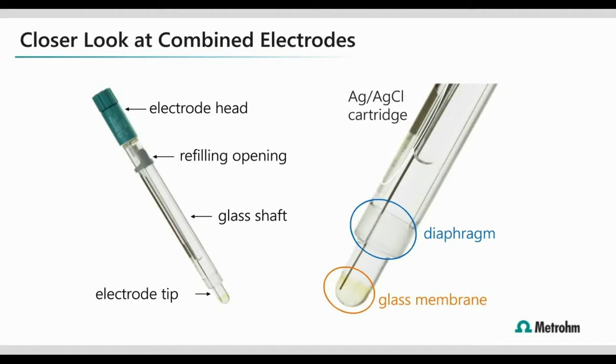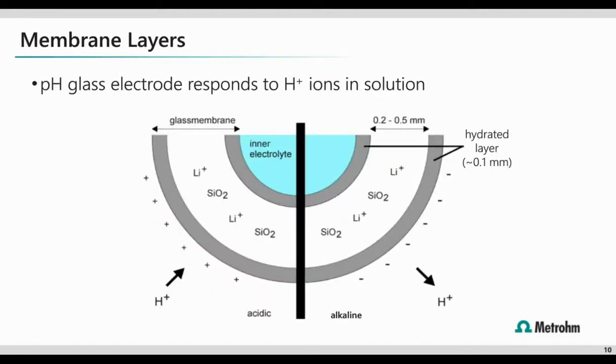Lastly is the electrode tip. This is the sensitive measuring area of the electrode, basically where the important stuff happens. The electrode tip is composed of the diaphragm, which is part of the reference electrode, and the glass membrane or bulb, where the actual sample measurements occur. In application instructions or general discussions, you may be asked, hey, is the tip of the electrode submerged? That means this entire area. So this is the portion of the electrode that must be in contact with the sample throughout the measurement or the titration. Now, because of the importance of each of those, that membrane and diaphragm, we're going to go one level deeper with each of those portions.